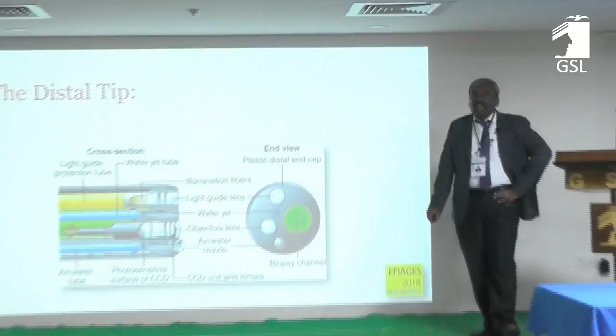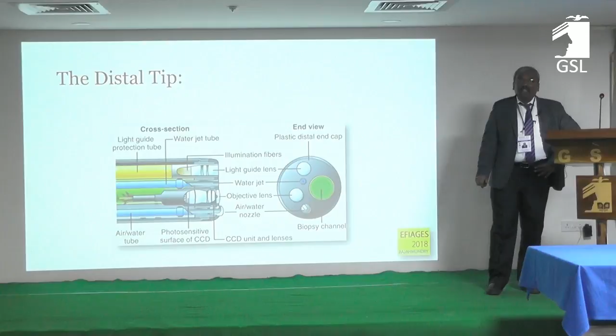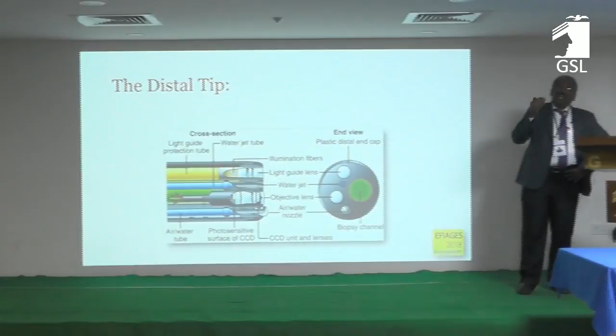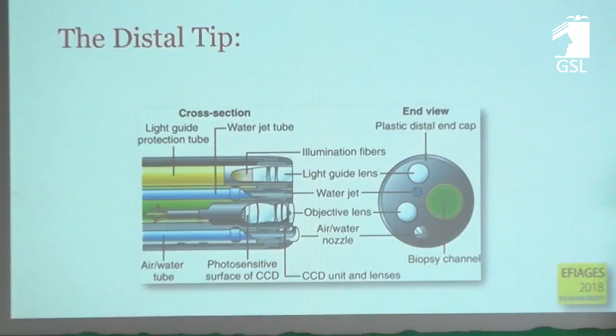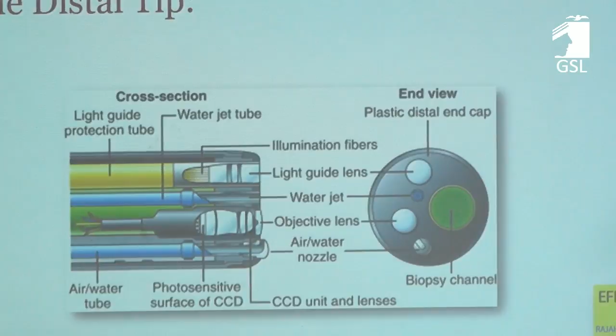Predominantly the largest is the biopsy channel. Usually it is 2.8 millimeter. Very rarely you may have even 3.2 millimeter channels, and there are some special devices like Apollo and others where they have tubes running along with the endoscope, because their devices are so very big, suturing devices, you can do endoclinch, all those things. They run along with the tube and not inside the tube. Those are all very advanced scopes.